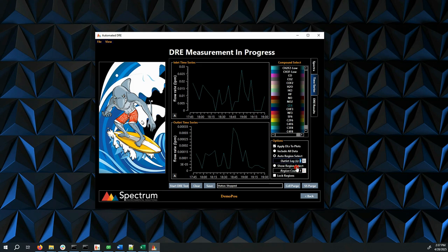And we've added this option. This is a lag in seconds. So this is if for some reason you have some residency time difference in the inlet and the outlet gas, and when it reaches the analyzer, you can institute a couple of second offset if, for example, it takes maybe 3 seconds longer for the outlet to register an event that the inlet already has registered, and you can also go backwards in time.